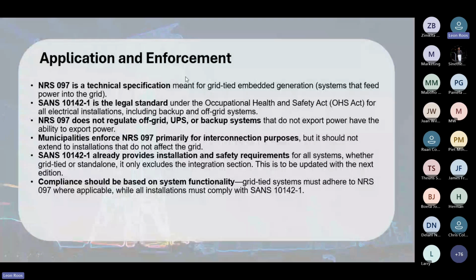Going a bit deeper: NRS 097 is the technical specification for grid-tied embedded generation, referring to inverters that have the ability to feed back or export power to the grid. A UPS-type system or off-grid system cannot export back unless it is faulty.